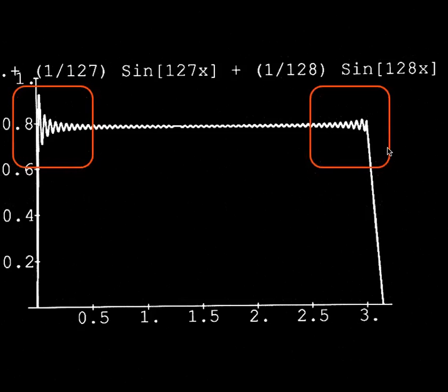So if it's a very steep gradient, that would be a high frequency sine wave. Not a very strong gradient would be a low frequency sine wave. No gradient would be the constant term that goes in the front. And therefore, from the signal intensity that comes back, we can calculate the coefficient that has to go in front of the sine waves, which the computer needs in order to be able to generate an image.